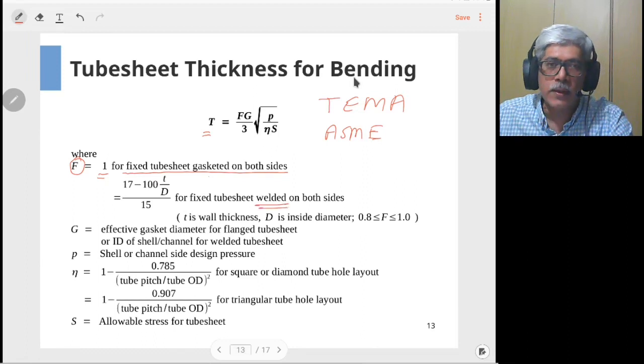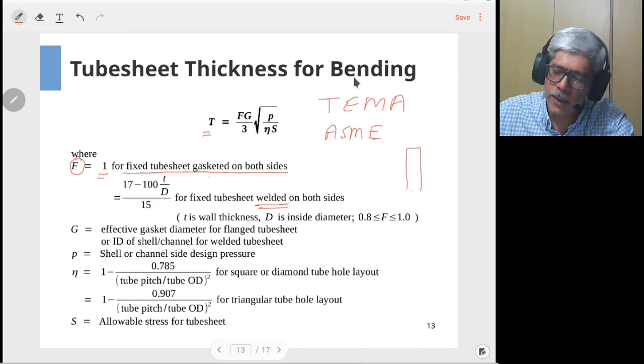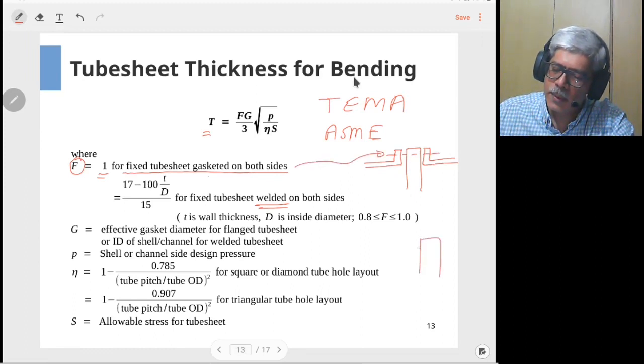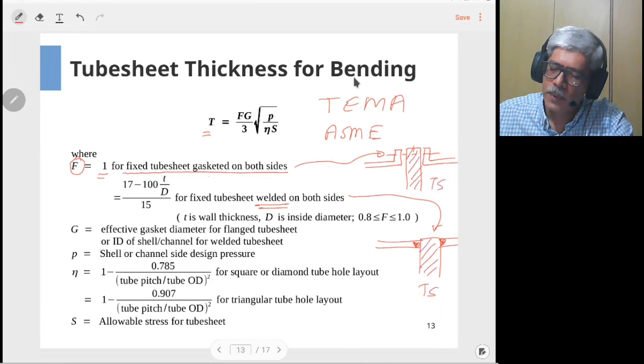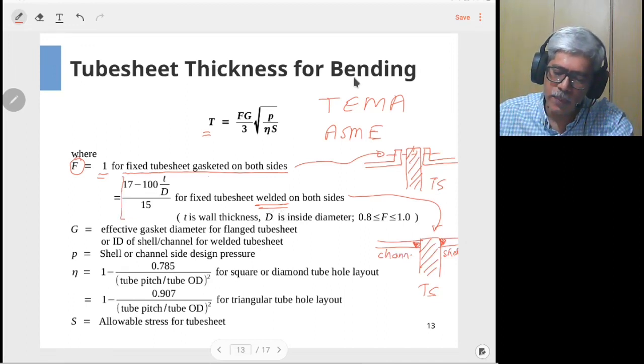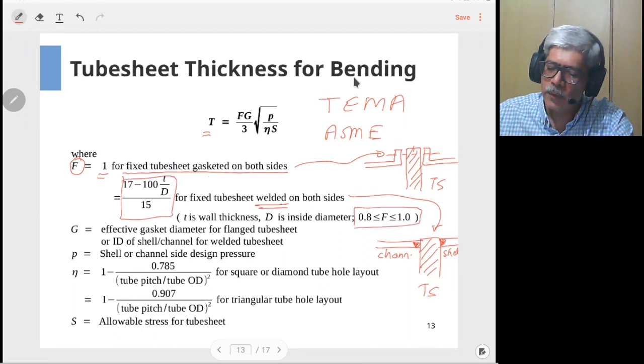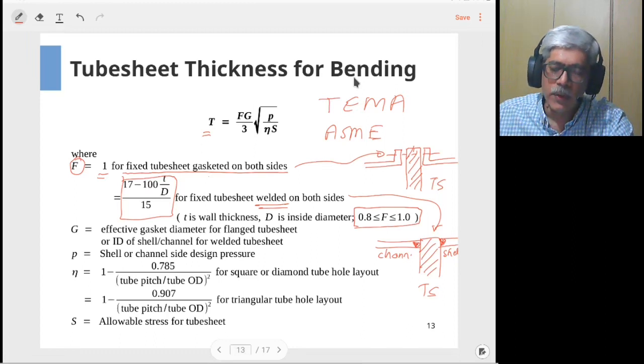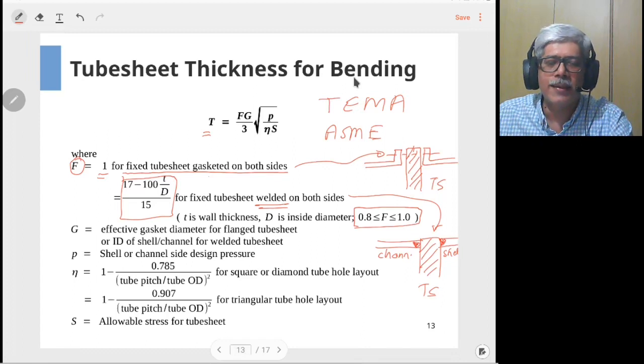In the case where the tube sheet is welded on both sides — where the shell side and channel side are welded to the tube sheet rather than bolted — the factor F is given by a different expression. However, whatever value you get from that expression, it has an upper and lower bound: if it is less than 0.8, consider it as 0.8; if it is more than 1, consider it as 1. This factor accounts for the stiffness offered on either side of the tube sheet.